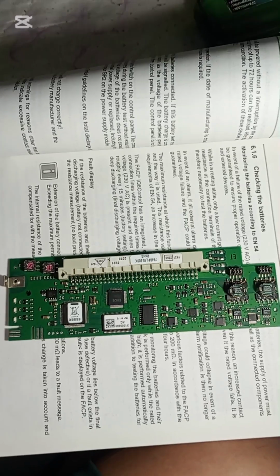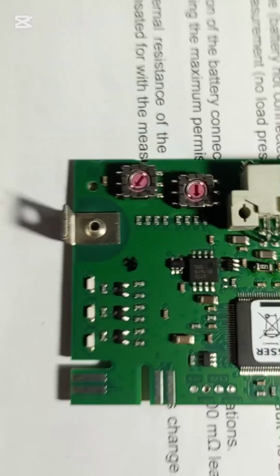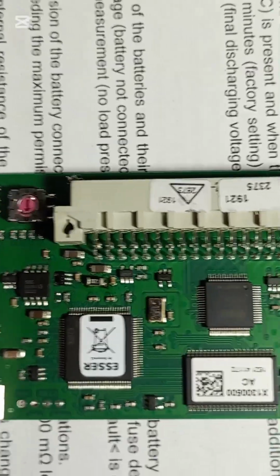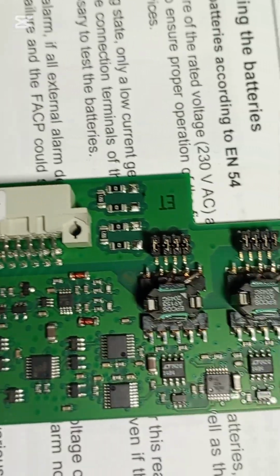So hello, right now I give you an example of the network interface card for the Esser Control M or Control C. As you can see, we have a switch 1 and switch 2 for addressing the network card. And the speed, as in these illustrations, we are using a 500 kbd or kilobaud rate. We have only two types of speed we are using in Esser: 62.5 kbd and 500 kbd.